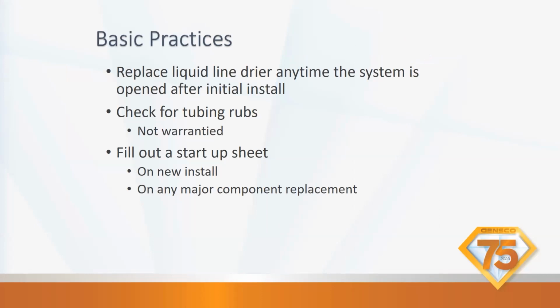410A oil will not boil off like R22 oil did. Okay, so you have to use a filter dryer on all of our systems, and it's because we don't know how much moisture is left in the pipes even after we do our evacuation. We can't get the moisture out of the oil. That's where I was going.